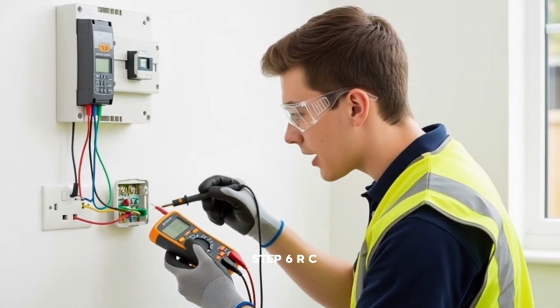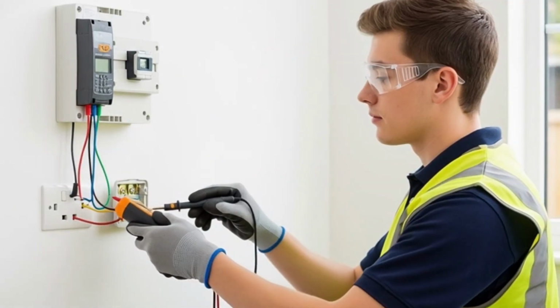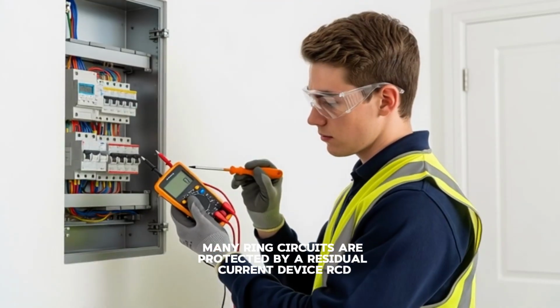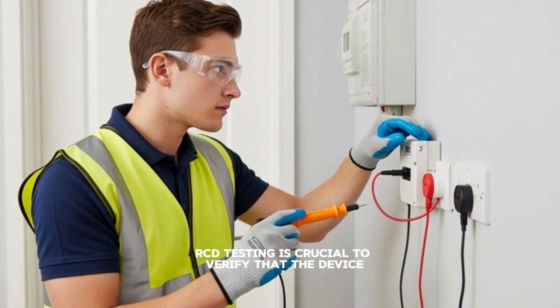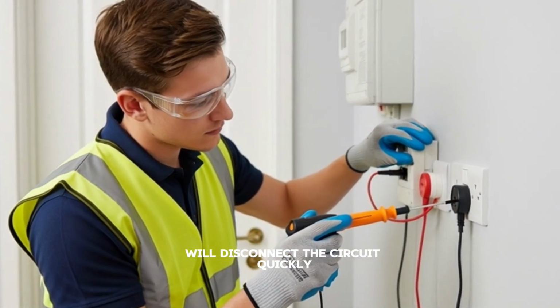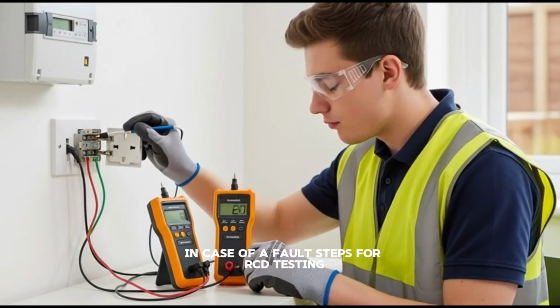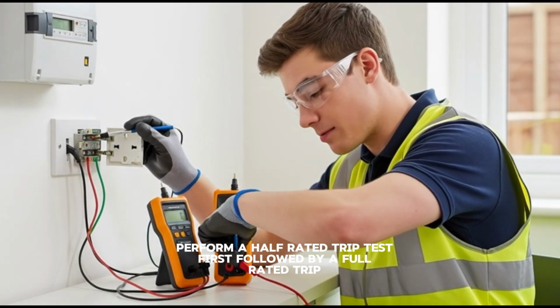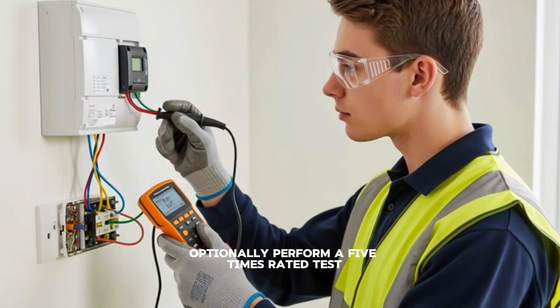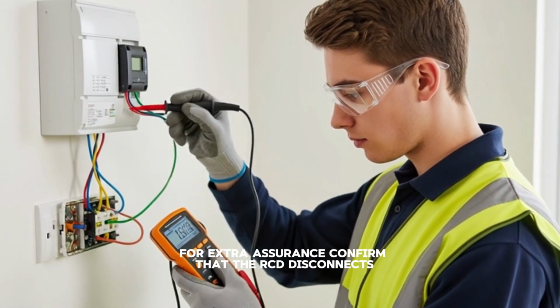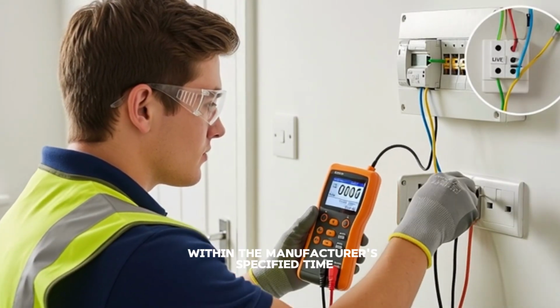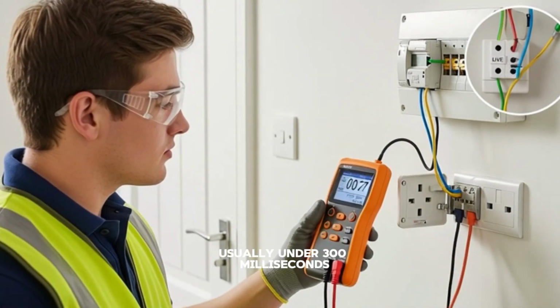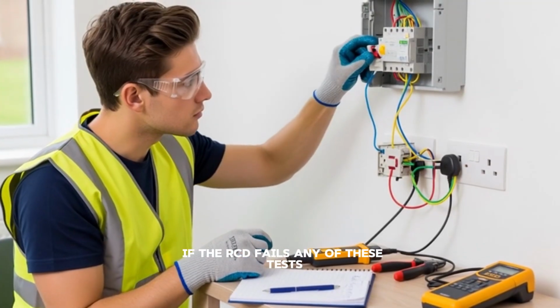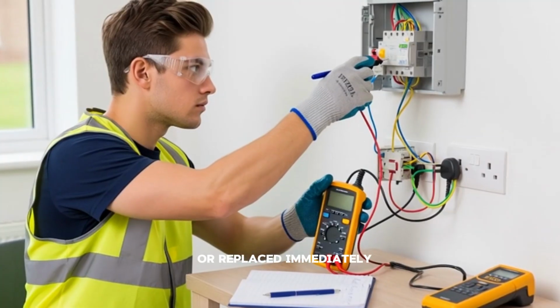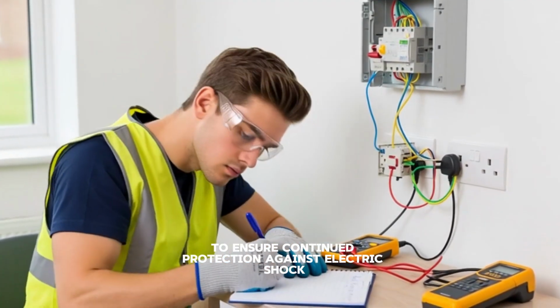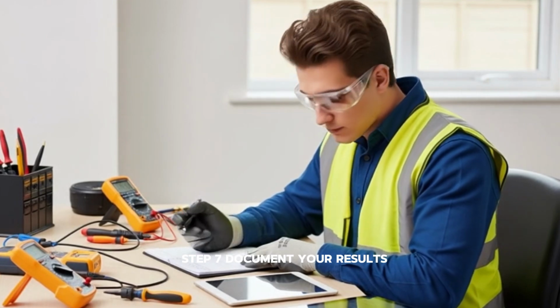Step 6. RCD testing, if present. Many ring circuits are protected by a residual current device, RCD. RCD testing is crucial to verify that the device will disconnect the circuit quickly in case of a fault. Steps for RCD testing: perform a half-rated trip test first, followed by a full-rated trip. Optionally, perform a 5 times rated test for extra assurance. Confirm that the RCD disconnects within the manufacturer's specified time, usually under 300 milliseconds. If the RCD fails any of these tests, it must be repaired or replaced immediately to ensure continued protection against electric shock.